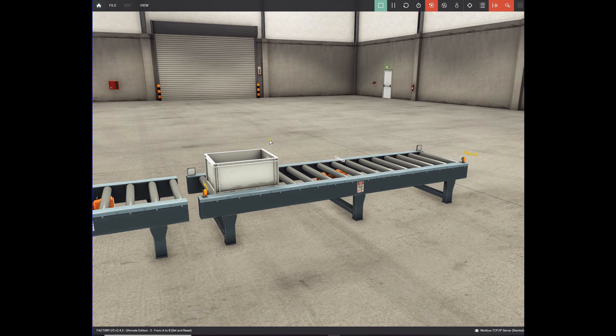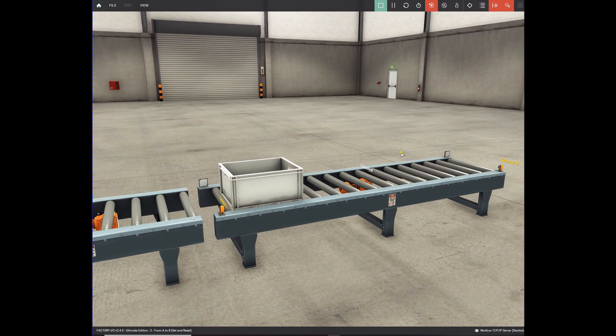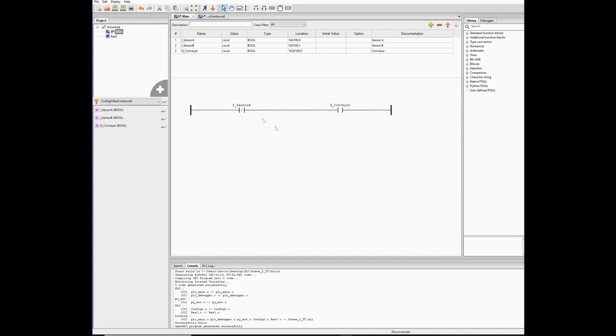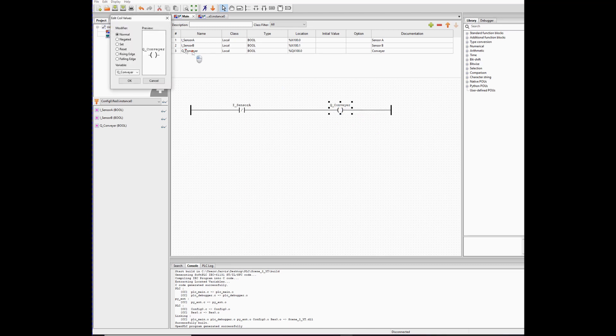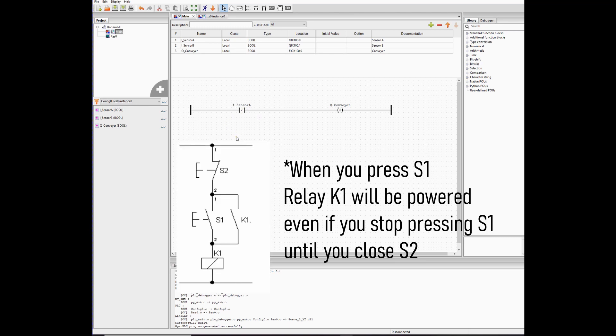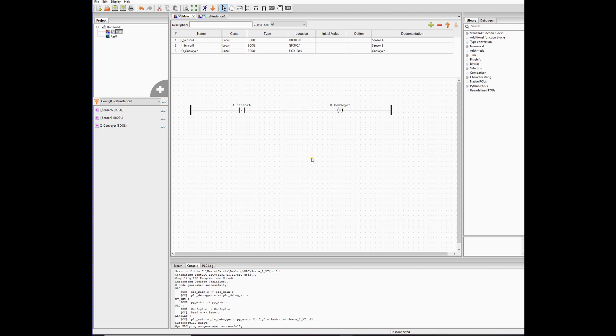Some of you might think of timers, but that's bad practice for situations like this. They made something called Set/Reset. You can set this output and it will remain set as long as you don't reset it. Double-click on the output and select Set. This comes from relay logic - you could do this with a relay where a contact over the relay keeps it activated. In PLC language it works like this, and it makes the transition from electrical to PLC easy and simple.